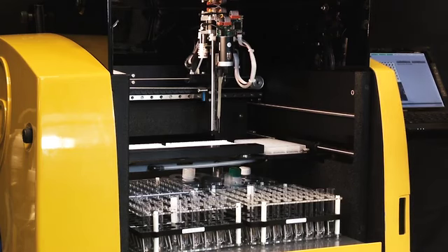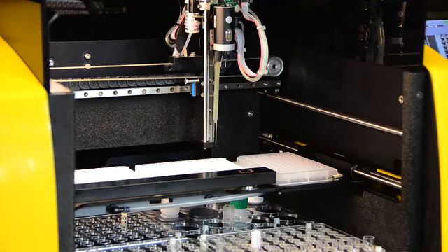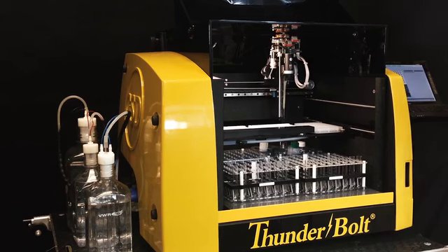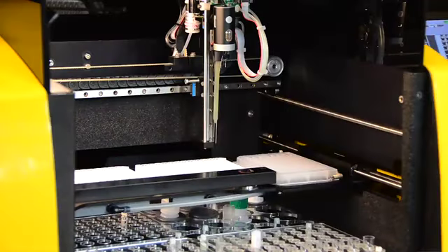The reason that we have such a great liquid sensitivity level is that we have a very sensitive liquid detection system. We use a direct current system that the instant it touches fluid, it signals the system and tells it what to do. So we can pick up lower volumes from lower dead volumes than any other instrument on the market. Our dead volumes for samples is anywhere from 100 to 150 microliters, and our dead volumes for reagents are anywhere from a half a mil to a mil max. Now these all depend on the type of sample tube, but I've seen anything as low as 1 microliter being picked up out of 30 microliters in the bottom of a 12 millimeter tube. So like I said, one of the best in the market.